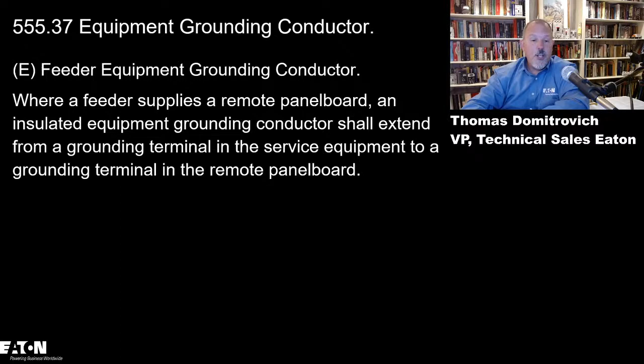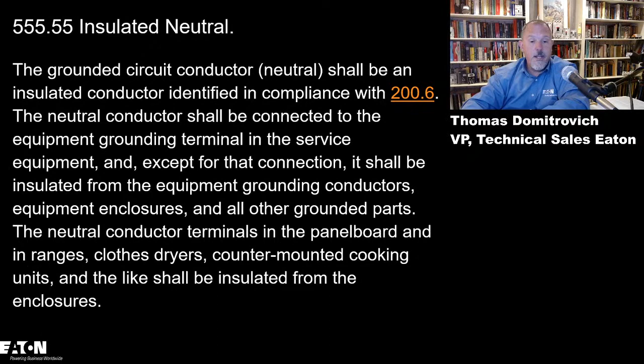On one of the inspections, we made certain to go and lift some panels and look for those green conductors. If you're inspecting these areas, you're going to be looking for the insulated equipment grounding conductors. They have to be out there. And there's some discussion about the grounded conductor: insulated conductor identified in compliance with 200.6, connected to the equipment grounding terminal at the service. So a lot of this is what we currently do already in regard to many installations.